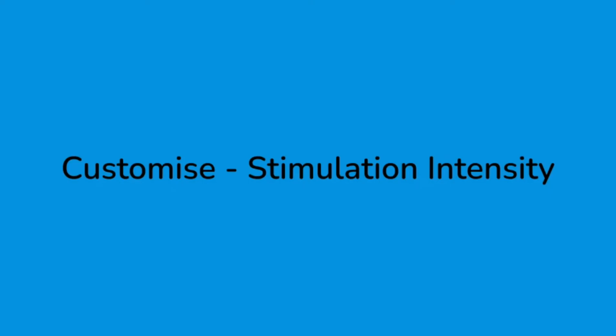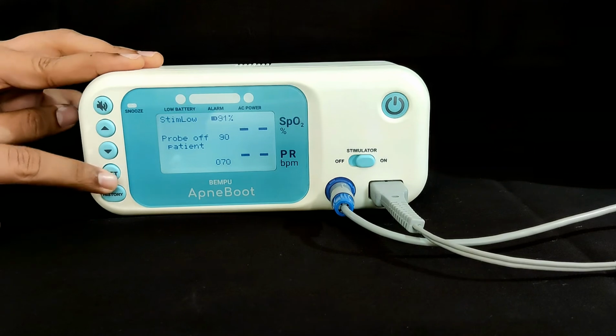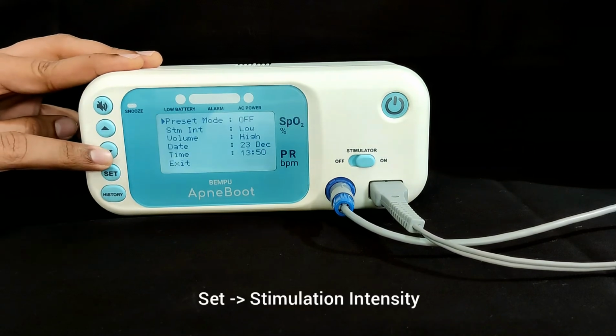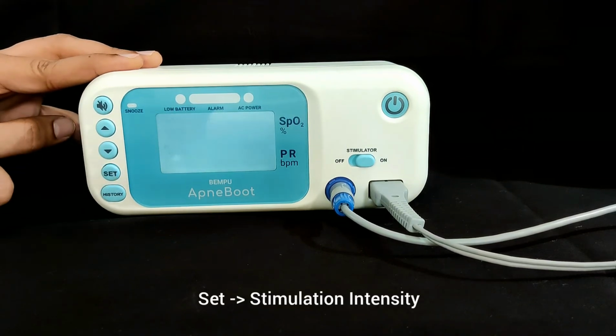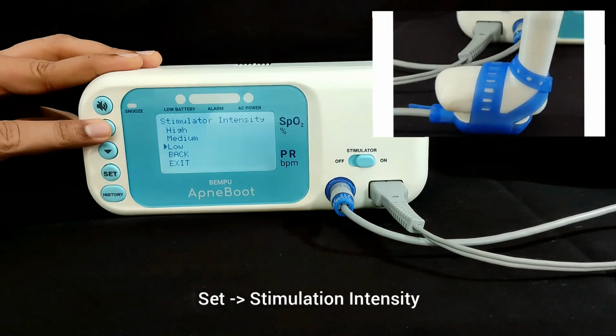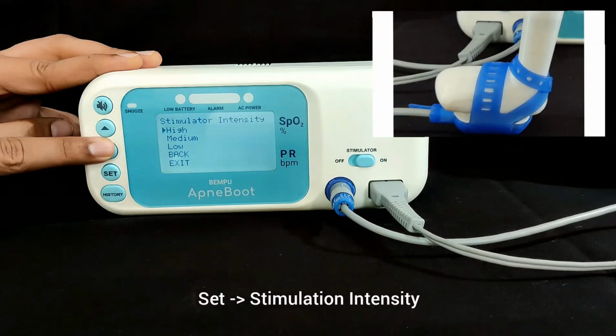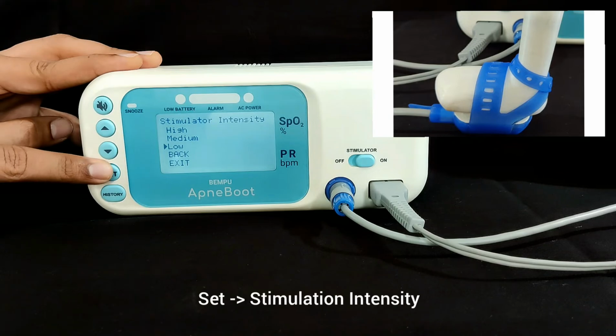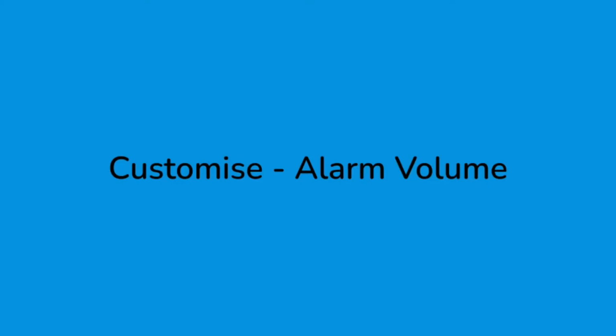You can also change the stimulation intensity of the vibratory stimulus as low, medium, or high. To do so, press the Set button, press the Set Intensity button, then select high, medium, or low intensity using the arrow up and down buttons. Press Exit to save the settings.